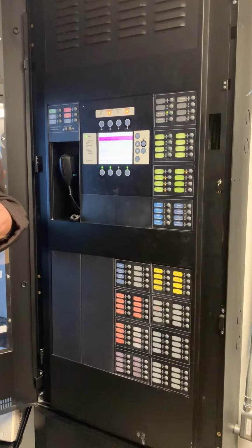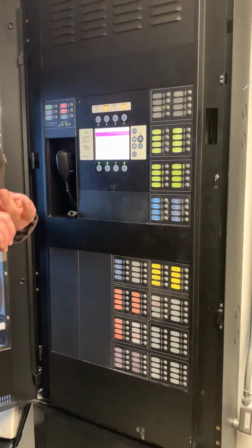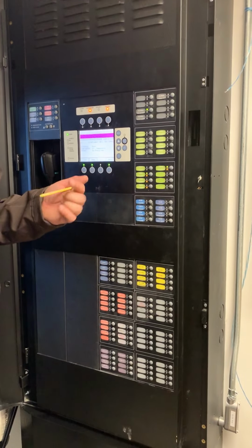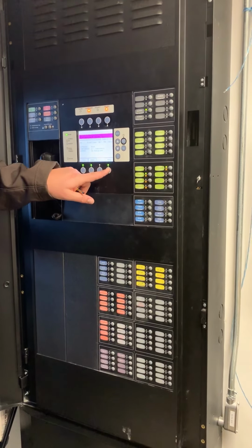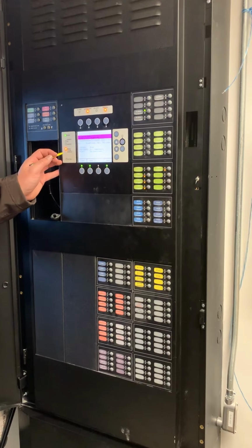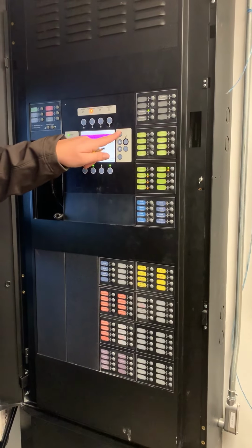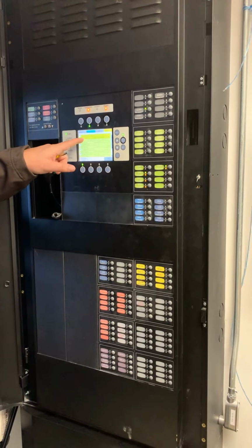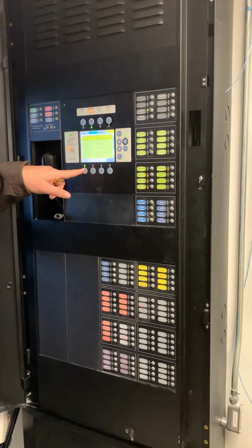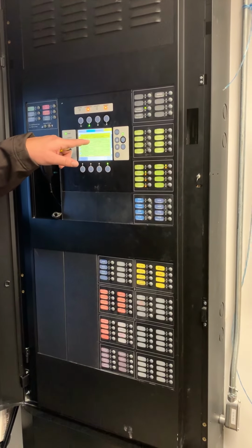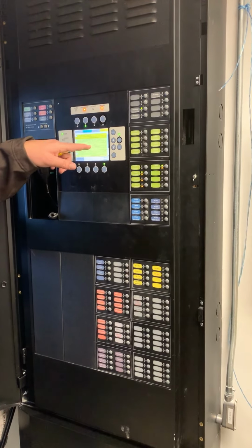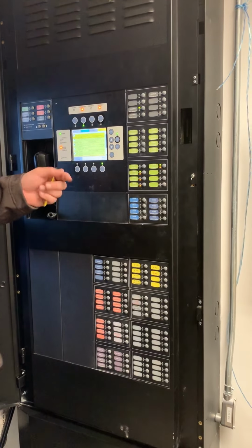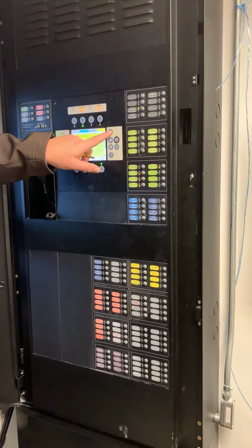So disarming a device, arming the device, doing your function keys, you always have to press execute after it's done to make sure it takes. And if I do execute, partial system disable light comes on and you get a trouble. Now I can go to menu, alert, and now I want to see the trouble that came in. That shows acknowledge my trouble, and that shows me 6 South SP water flow stair 5 input is disarmed. And then you reset your system. And that's how you do it on this panel.